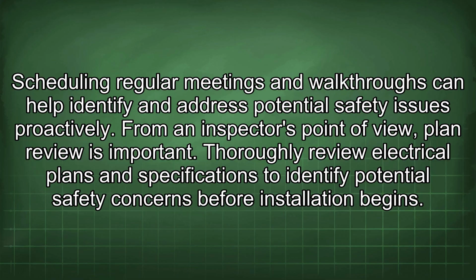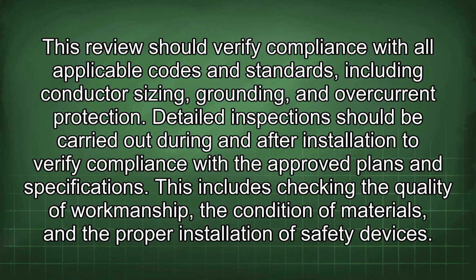From an inspector's point of view, plan review is important. Thoroughly review electrical plans and specifications to identify potential safety concerns before installation begins. This review should verify compliance with all applicable codes and standards, including conductor sizing, grounding, and overcurrent protection. Detailed inspections should be carried out during and after installation to verify compliance with the approved plans and specifications. This includes checking the quality of workmanship, the condition of materials, and the proper installation of safety devices.